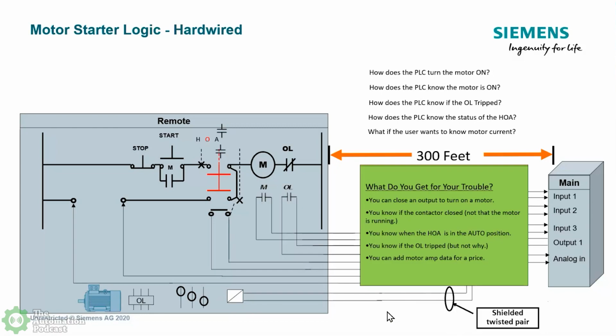So some guys in the applications that are listening today, they do speed sensors, which they would put on the head pulley or depending on where they wanted to notice it. But then also they could set some limits on the current draw, that if it's unloaded, you could see the current's maybe at 20% of full load amps and so forth and so on. And that would give them some indications. But really, with a starter, you don't have any real intelligence telling you exactly how things are going at the motor and if it's running okay.